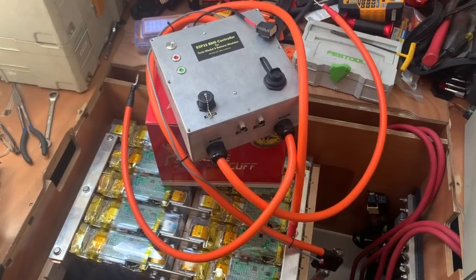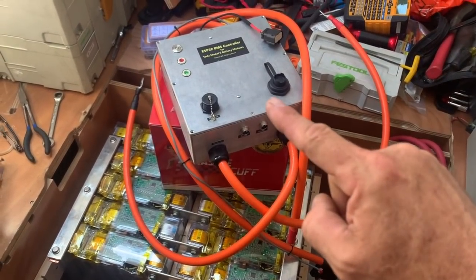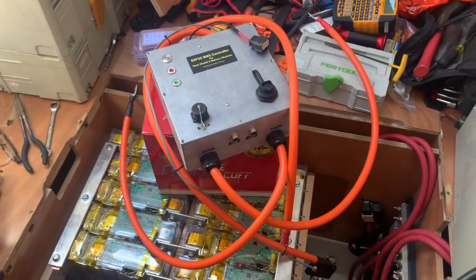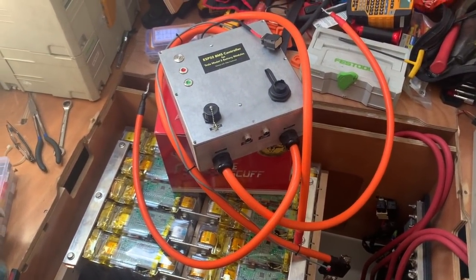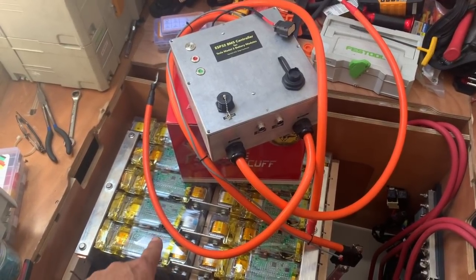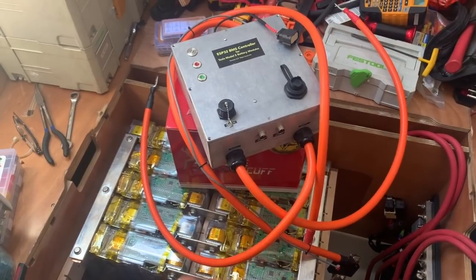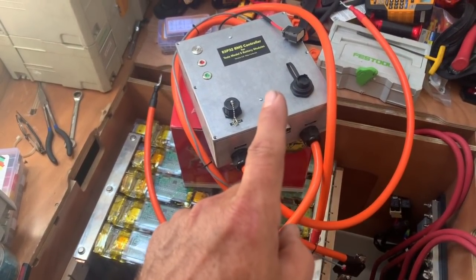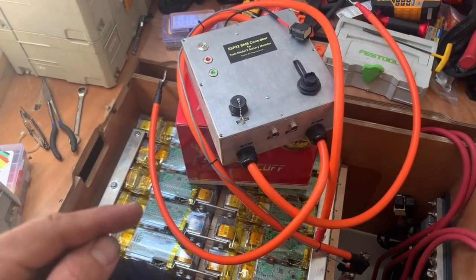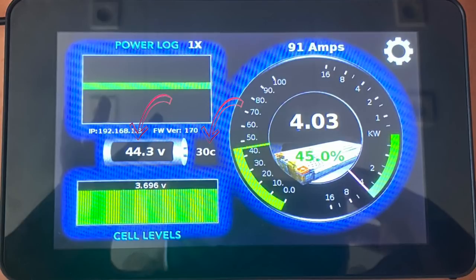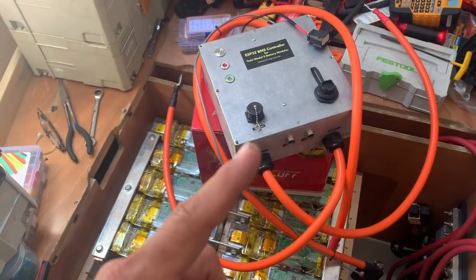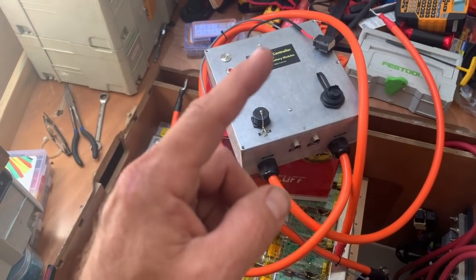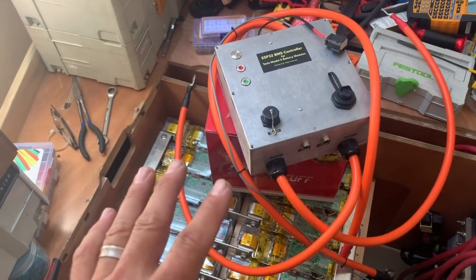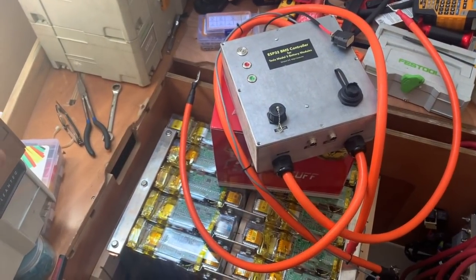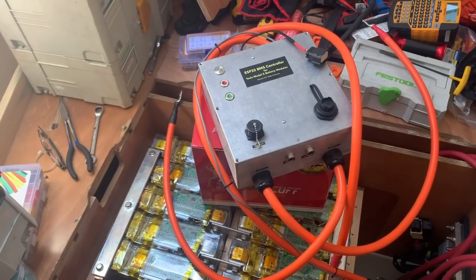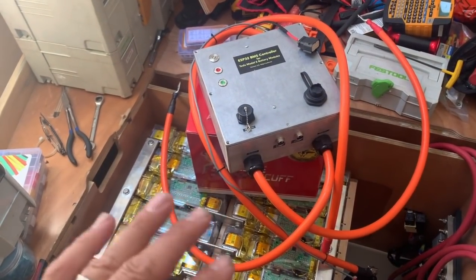All right guys, this little box right here from EVTV is a BMS Monitor and Controller. We are using all of the BMS boards that Tesla installed in the batteries from the factory. This box, along with a controller I'll show in a bit, monitors all of the data coming out: temperature, voltage, every parameter they have. It feeds into this box, which runs off circuitry on the inside, and if there are any issues in the battery anywhere, a big contactor shuts off all of the power. Our Victron inverter charger also shuts down the entire system if anything has an issue.